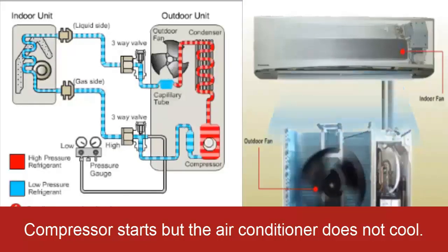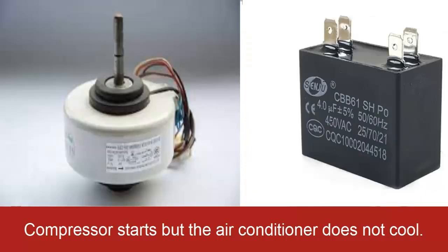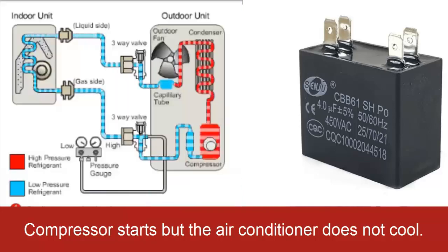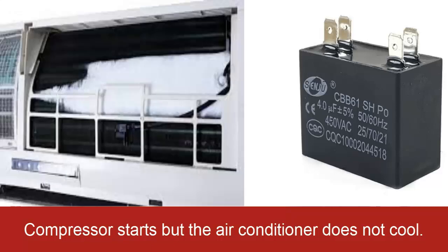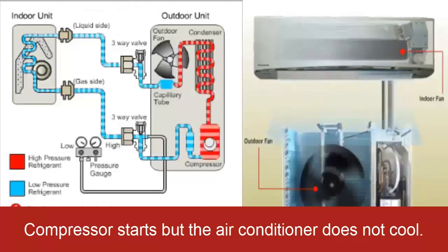6. Problems with the fans. If one of the fans, whether the condenser fan or the evaporator fan, stops or spins slower than normal, the unit may experience inadequate pressure. This can result in poor performance or evaporator freezing. Check the fan capacitor and bearings. If it is a serious fault, the fan should be replaced.